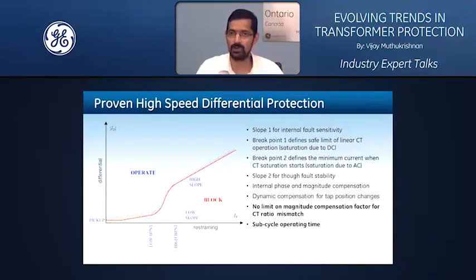slope, dual breakpoint with a spline characteristic in between the two breakpoints. Here, essentially, slope 1 you set for internal fault sensitivity. Your breakpoint 1 defines the safe limit of linear CT operation. Breakpoint 2 you set around the minimum current when CT saturation starts. Your slope 2 is more for through fault stability. This is the transformer differential algorithm that is proven for a decade plus years in GE products.